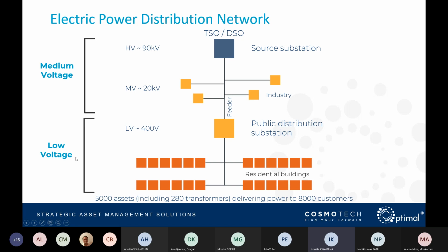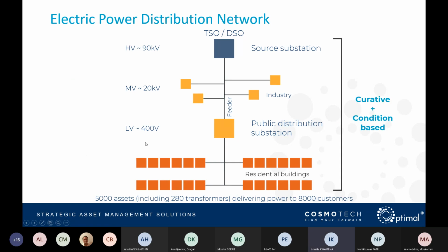It is therefore advisable to reduce the expenses on the low voltage transformers where the risks associated are quite low. Also for this network, where most of the assets employ a run to failure strategy, the only asset group which could be subject to a budget cut is actually the transformers, since they have preventive and condition monitoring maintenance on them. The challenge here, however, is to reduce the budget, but also make sure that the corporate objective is met.